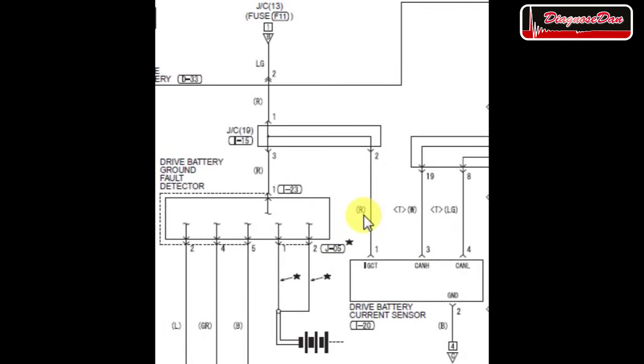Let's start with the red power supply. The power supply is shared internally between the ground fault detector and the current sensor. The BMU is not flagging a code for the ground fault detector, so we can assume this sensor is working fine. If this sensor is working, this means the power supply is making it into the battery.